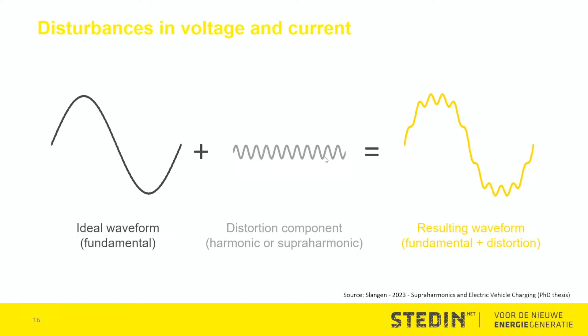In the past, distortions were mainly low frequency, so that's what we call harmonics. That's an example in the top figure. These are disturbances with a frequency below 2 kilohertz that are at a multiple of the fundamental, so it's quite easy to measure and look into. It's also really well covered in standardization because harmonics have been known for several decades. So that issue is quite under control, I would say.